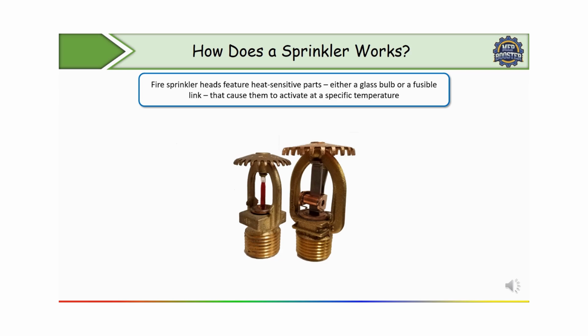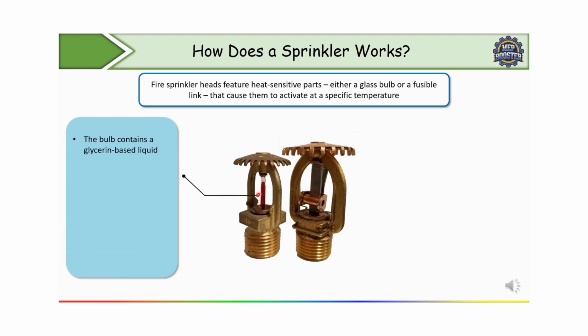Fire sprinkler heads feature a heat sensitive part, either a glass bulb or a fusible link, that causes them to activate at a specific temperature. Here in the first image, this one is the glass bulb, the heat sensitive element, and here we have a fusible link. See how they work. Simple. The bulb contains a glycerin based liquid. Once the air around the sprinkler reaches a certain temperature, 68 or 93 degrees Celsius, because inside the glass bulb we have a different color of liquid based on the temperature rating, the liquid expands, which causes the glass to break and water is released from the sprinkler head.